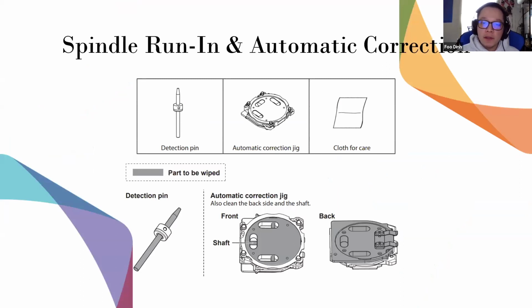This detection pin, these are blown up photos, so you know what they kind of look like. Okay, and these are the certain areas that need to be cleaned when you're doing the calibration, after you use the mill, if there's zirconia dust or anything like that. Two parts: generally the entire detection pin itself, and the correction jig or the calibration pocket, as they say. You can clean it with the cloth that they give you, or with a microfiber cloth. Either way, it's not going to hurt it.